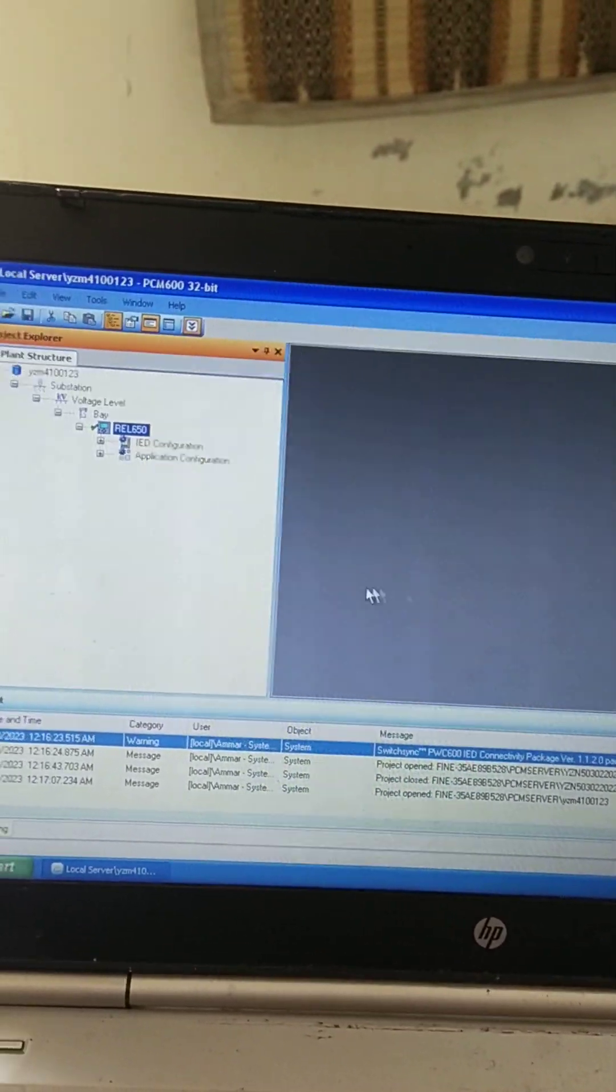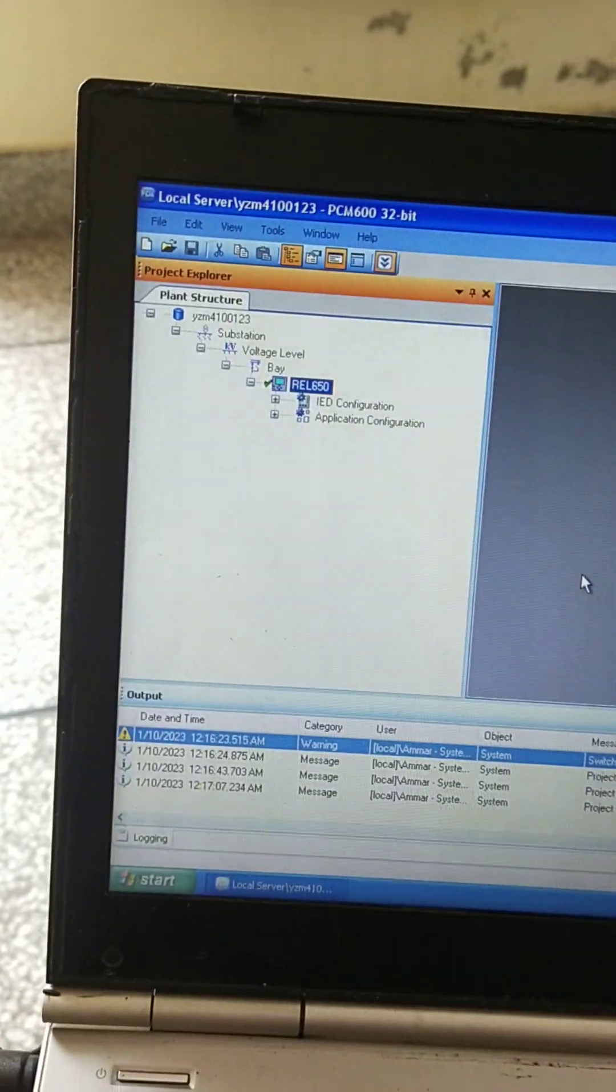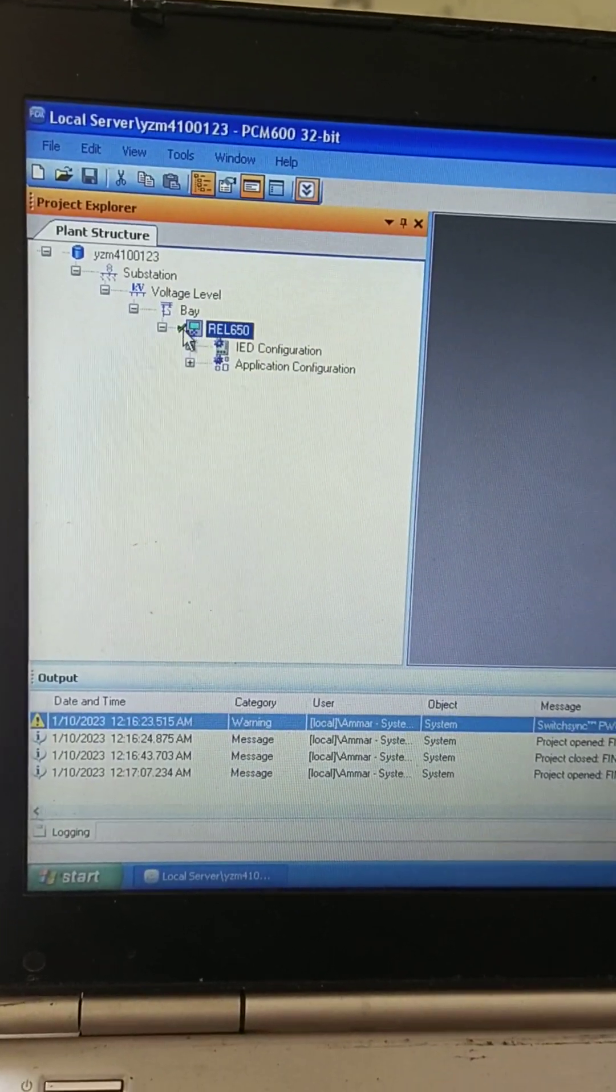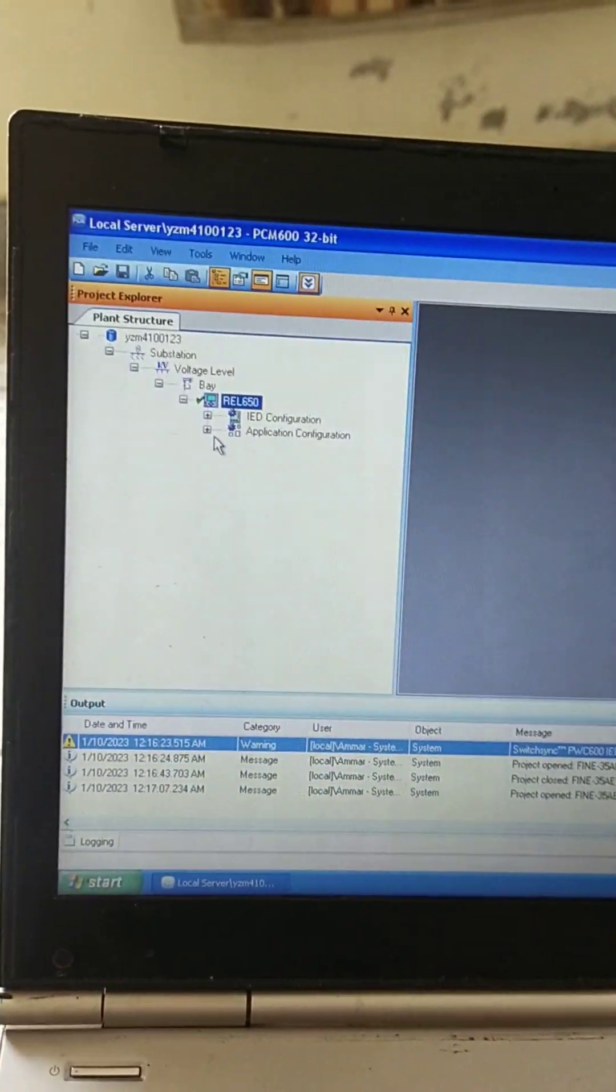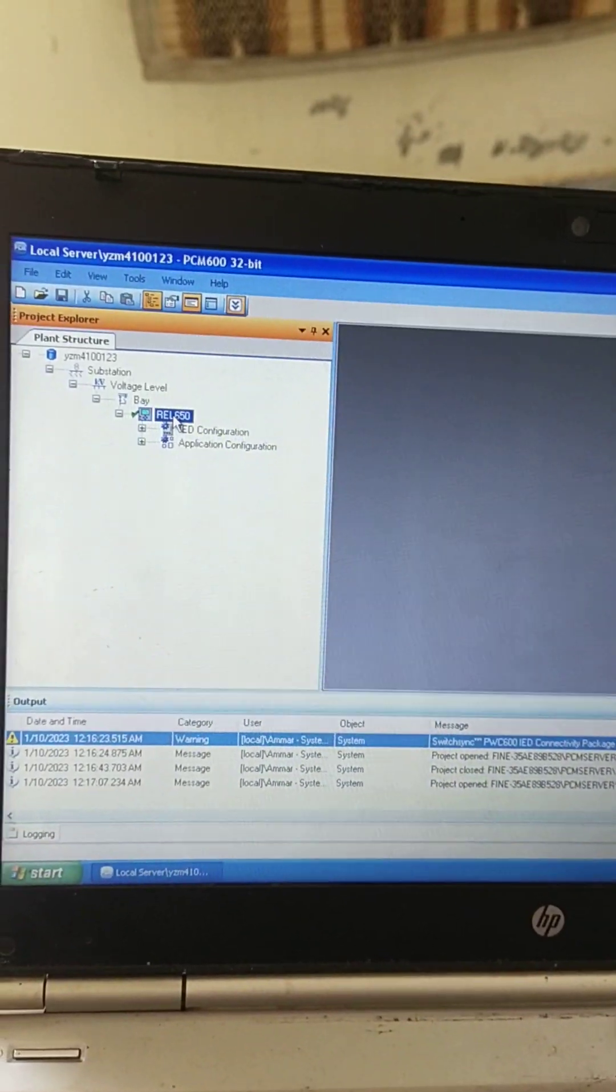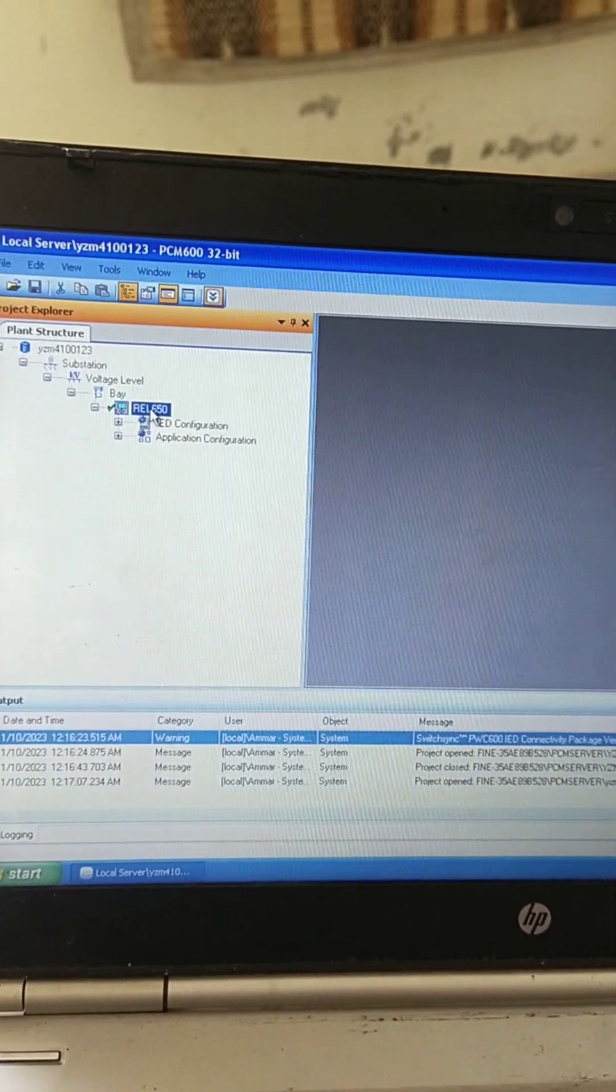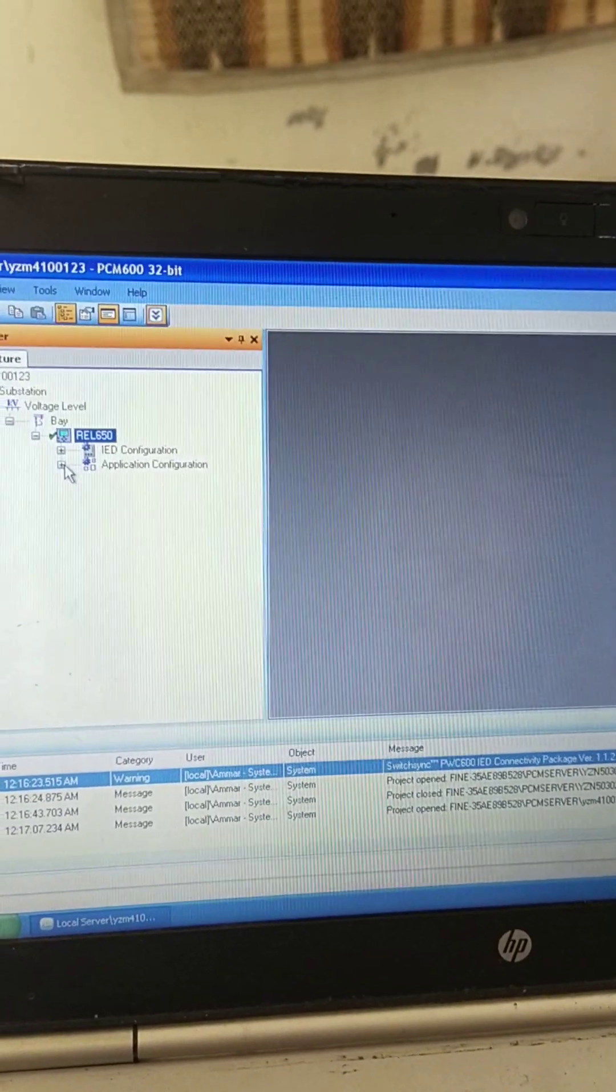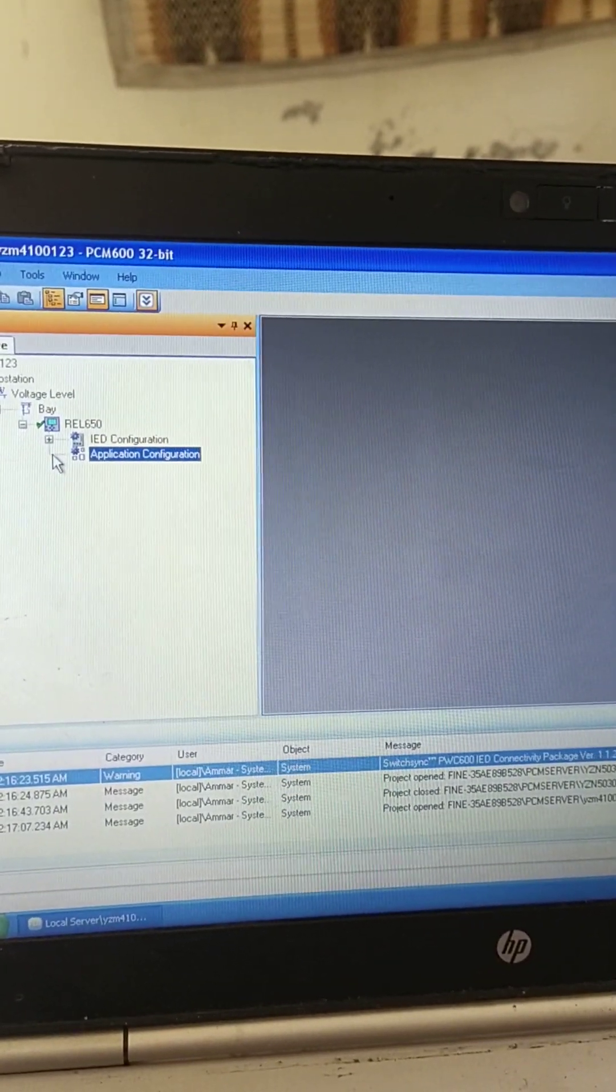So our relay is communicated properly. When relay is communicated, this will go into green. The most important part is always after communicating, read the settings from the device. If you directly go to the settings, for example from here...